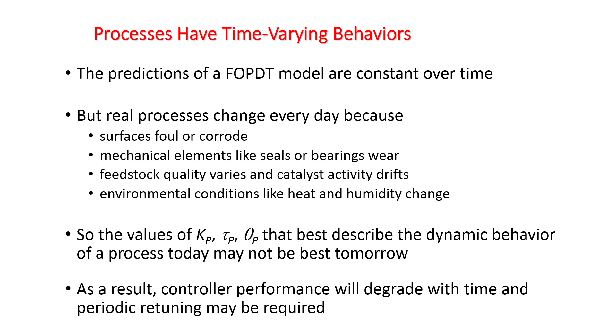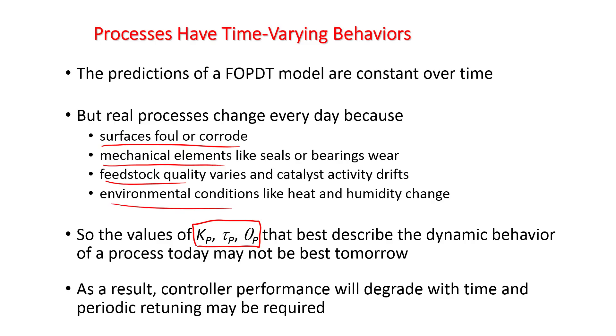The values of k_p, tau_p, and theta_p may change over time due to fouling, corrosion, mechanical wear, feedstock changes, or environmental conditions like temperature and humidity. When these change, you may need to go back and retune the controller because the fundamental response of the system has changed.